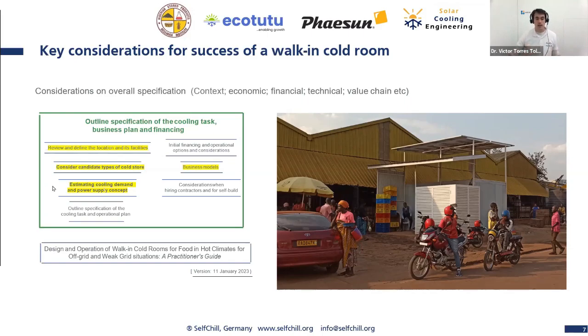That's crucial. Then we need to consider which types of cold storage we are going to use. Are we going to use one chamber, two chambers? Are we going to use solar PV, or do we have access to the grid? Do we want to do thermal storage, and so on? And right after that, the next thing we need to do, and this you will see at the end of this webinar, and especially also in the next webinar, is the estimation of the cooling demand and how to deliver the power. And I can tell you in advance, it makes a huge difference how you use the cold room. It makes a huge difference if you are entering half a ton per day or 1 ton per day. That will make your cooling demand much higher, and therefore also the amount of PV panels that you might need, and the investment you need to make.